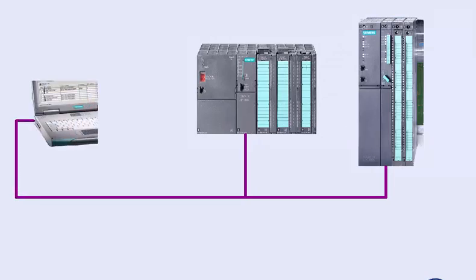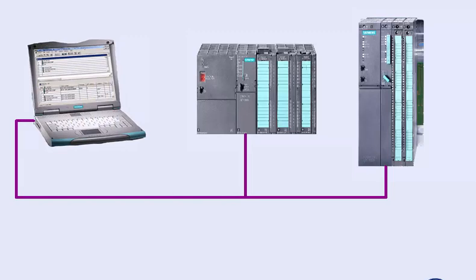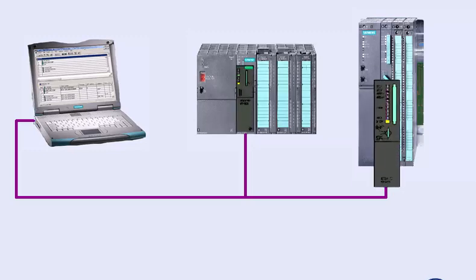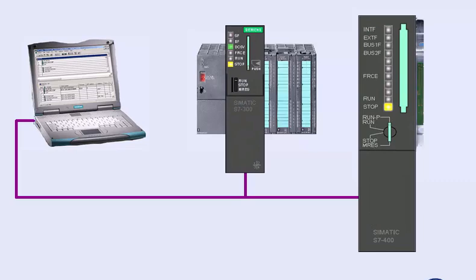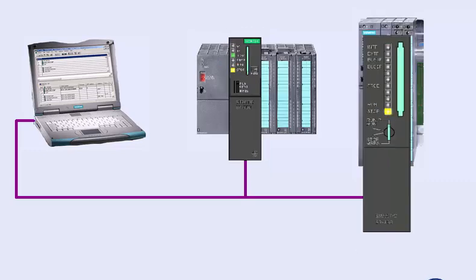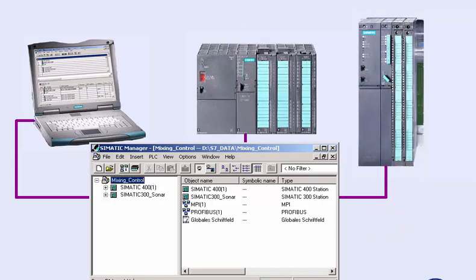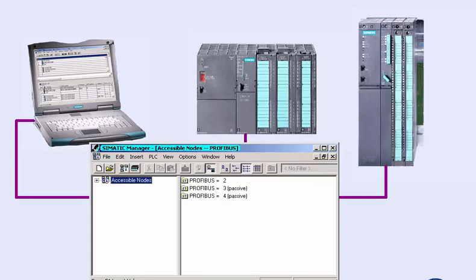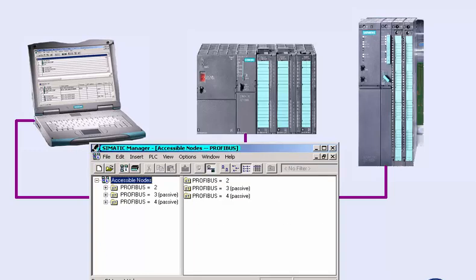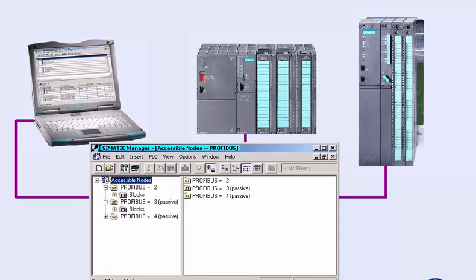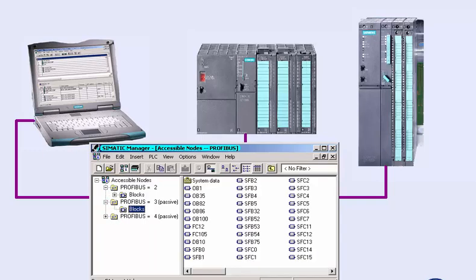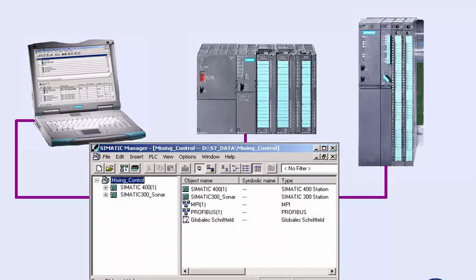The programming device is connected at the PROFIBUS and the PROFIBUS station addresses of the automation devices have been set according to the plant configuration. After switching on the supply voltage, the LEDs at the front of the CPU indicate the operating mode. The power is on and the CPU is in stop mode. The accessible nodes function of the SIMATIC manager shows us all the modules accessible at the bus system and their addresses. This gives you a quick overview of which bus stations are already accessible with the programming device. This allows you to easily trace a faulty station configuration and correct it.